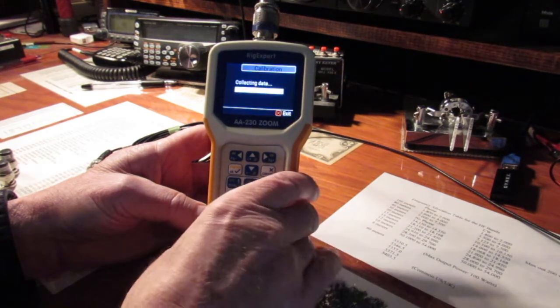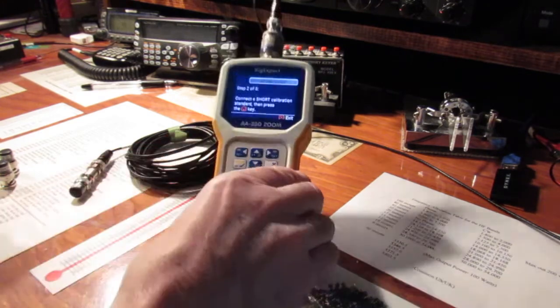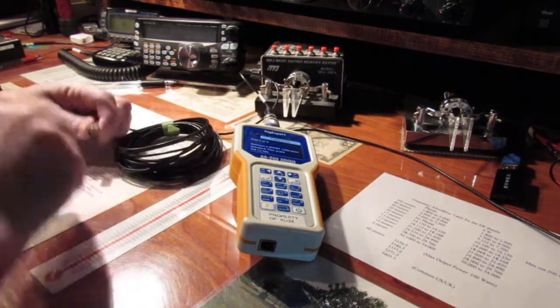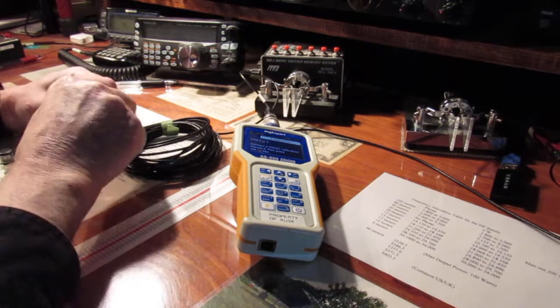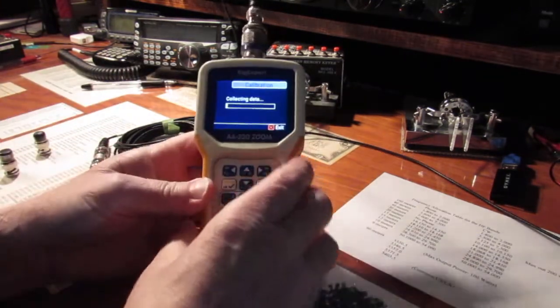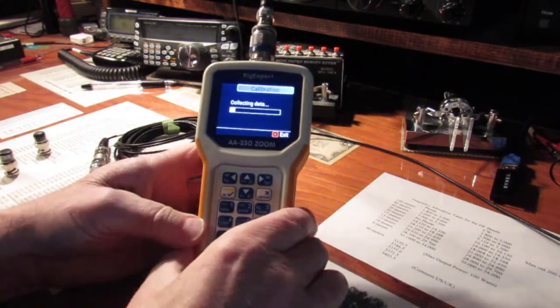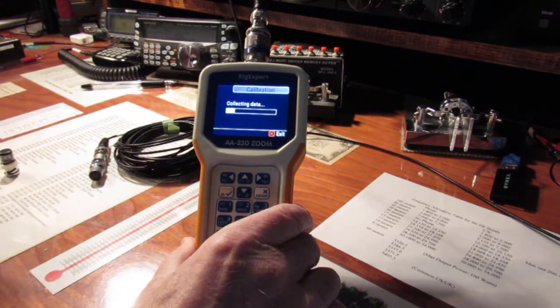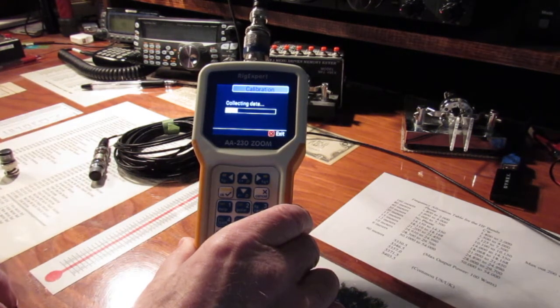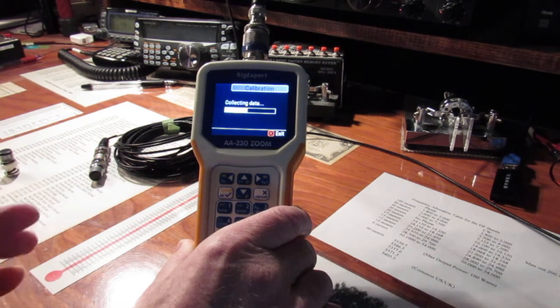So there's the open. Now it's going to tell me to put the short. So we take the open off, put the short on, push the button, we'll get it going. And then the next one is going to be the load. So we did the open, that's the short. And you really want to do this at 500 sampling points for a degree of accuracy.